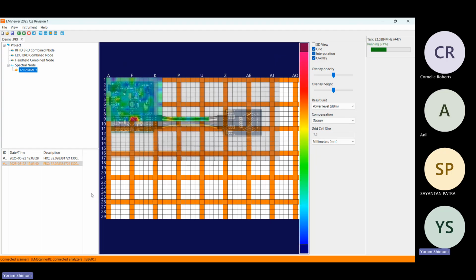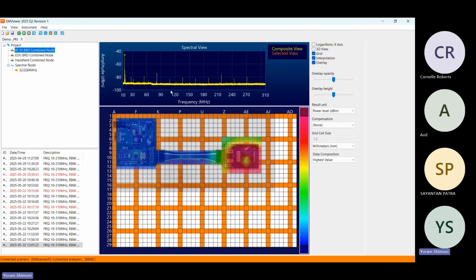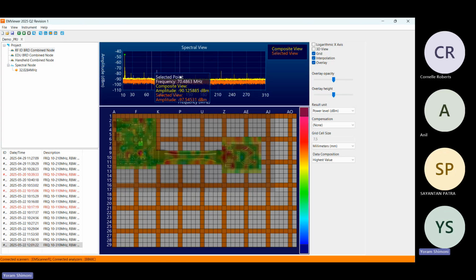32 megahertz scan. So the next mode of operation, the one that I showed you, is this one. This one is the combined one. Now, this one is the slowest, but contains a lot of information, because you can select a certain frequency, or you can select a certain location and see the response of that location. Now, you can also copy the image to clipboard.